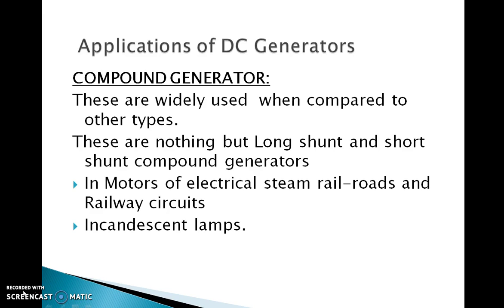Compound generators are further divided into long shunt and short shunt, and further into cumulative or differential types. The cumulative compound generator is the most widely used DC generator, because its external characteristics can be adjusted to compensate for voltage drop in line resistance. Such generators are used for motor drives requiring DC supply at constant voltage, for lamp loads, and for heavy power services such as electric railways.